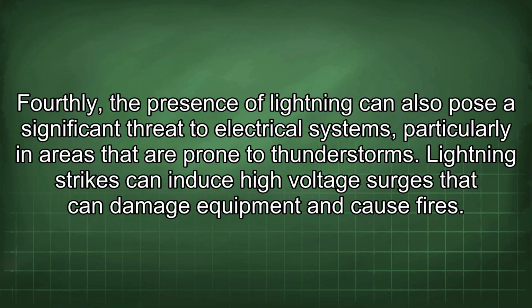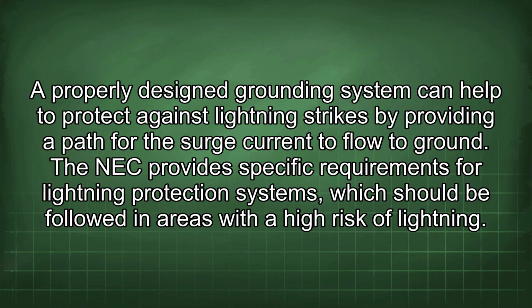Fourthly, the presence of lightning can also pose a significant threat to electrical systems, particularly in areas that are prone to thunderstorms. Lightning strikes can induce high voltage surges that can damage equipment and cause fires. A properly designed grounding system can help to protect against lightning strikes by providing a path for the surge current to flow to ground. The NEC provides specific requirements for lightning protection systems, which should be followed in areas with a high risk of lightning.